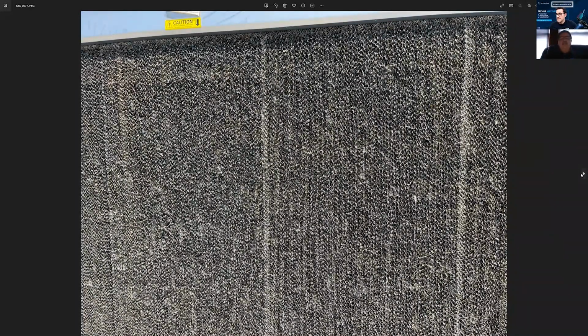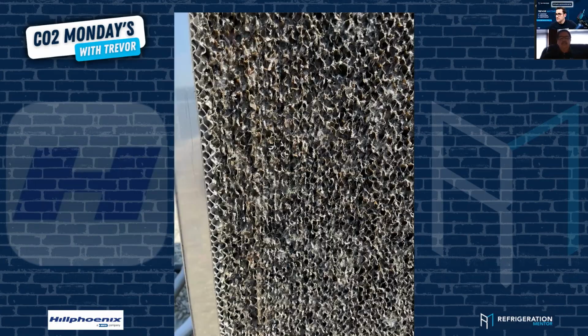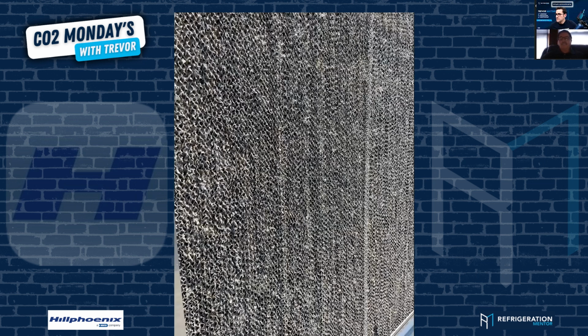So maintenance. This is actually a BAC condenser unit with the pads on the side. These pads are what I would like to call non-functional. They've probably been out of service for a couple of years. You're beyond the ability for the cellulose to absorb the moisture and help to evaporate as it passes through. Maintenance, guys. These CO2 racks, just like any rack, you got to do the maintenance.